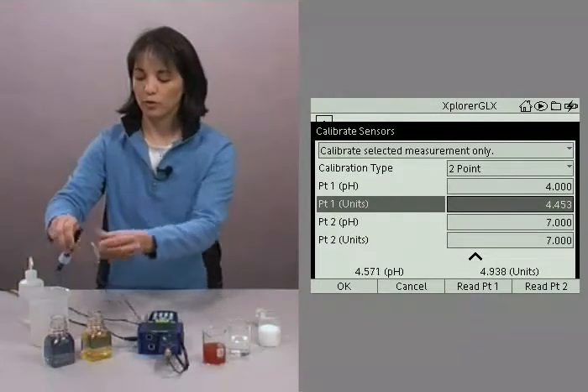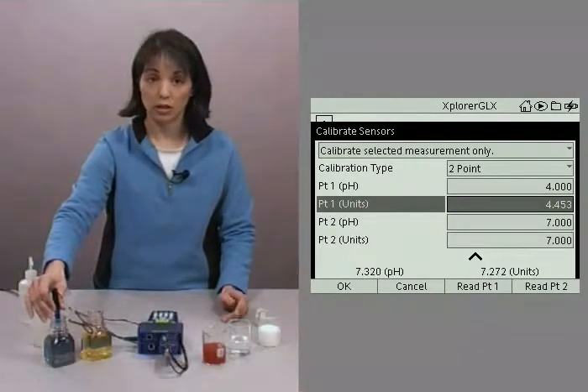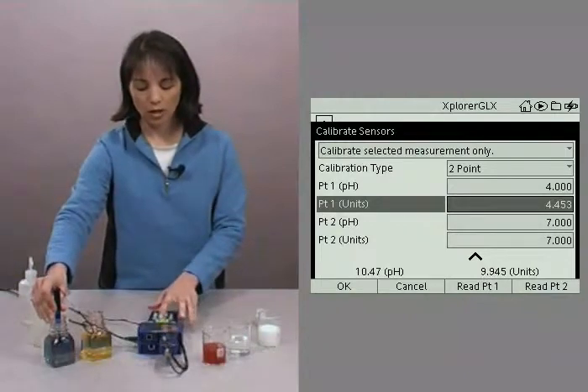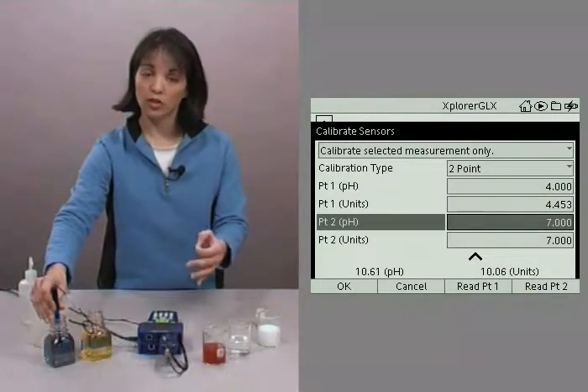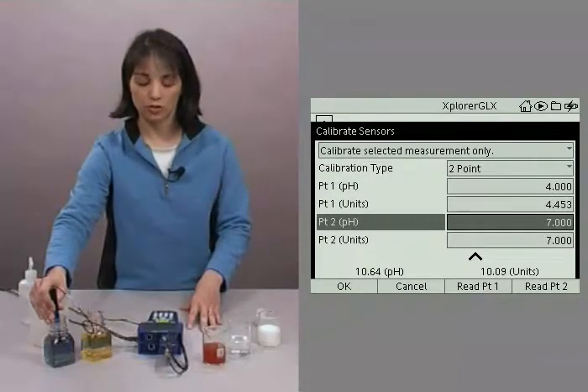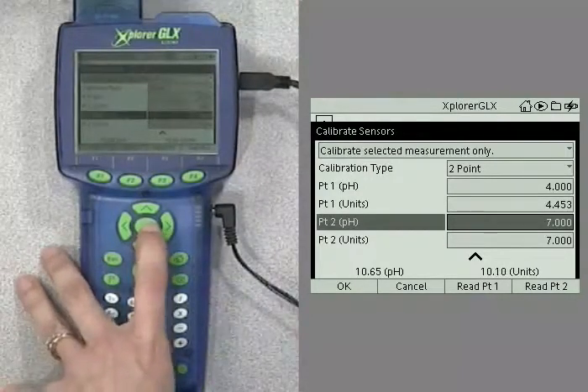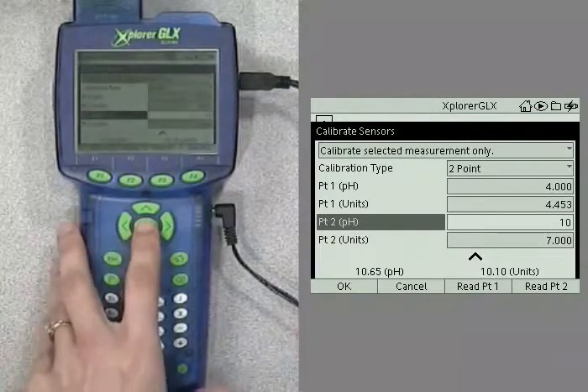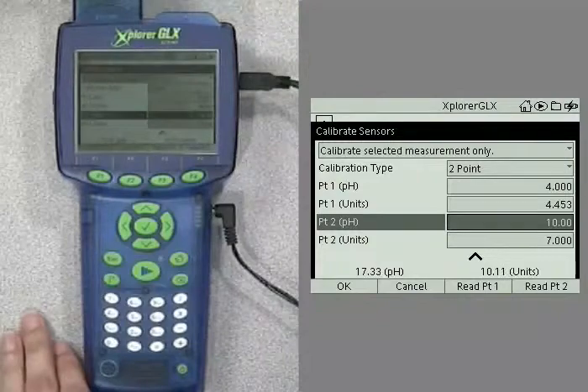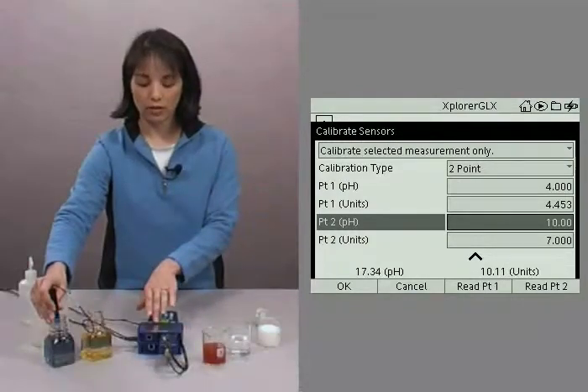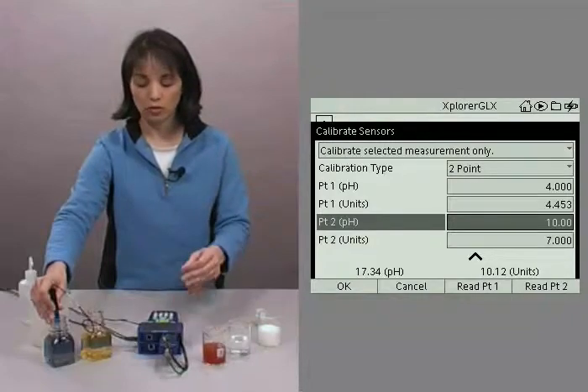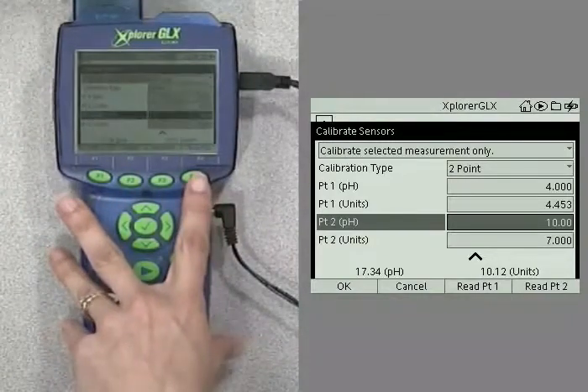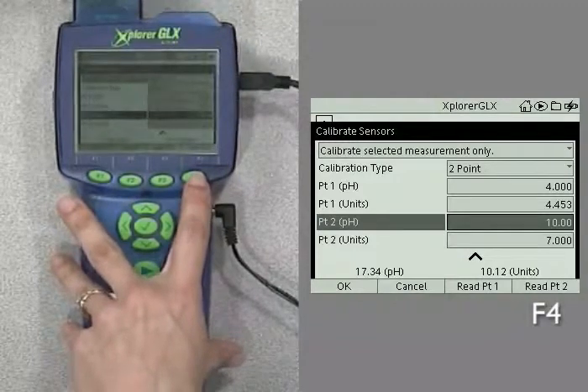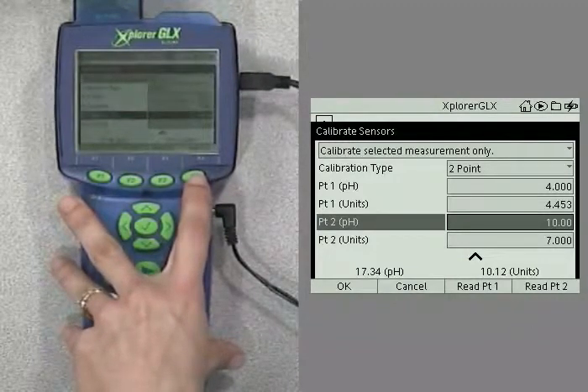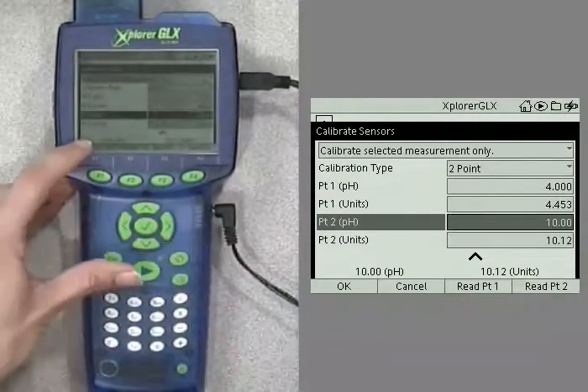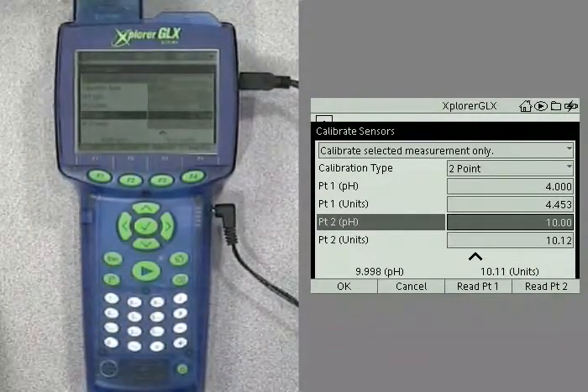So we will put our probe into our pH 10 buffer solution, and we need to first tell the Xplorer GLX that this is a pH 10 solution, not 7 like it says there. So push the check mark and type in 10 and push the check mark again to accept that change. Okay, transfer the value that it sees there, which is 10.11 for the raw units, into that second field by pushing not the F3 button, but this time the F4 button, which lets the Xplorer GLX read point 2. And when you do that, you see that our live reading is now the correct one.